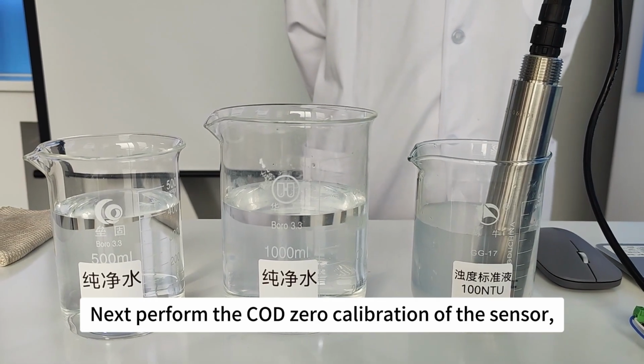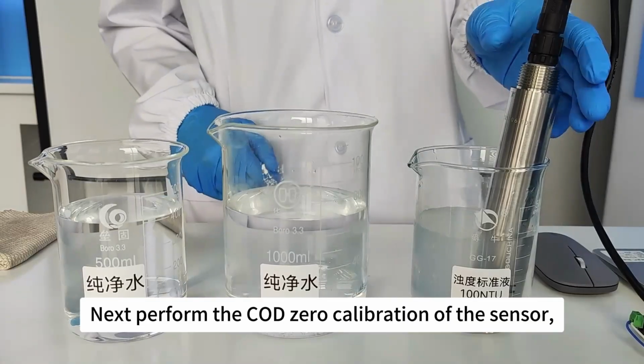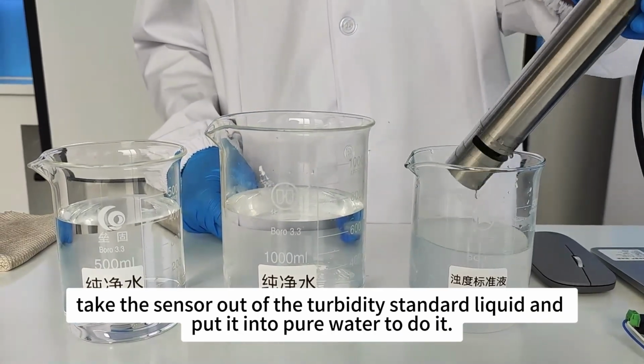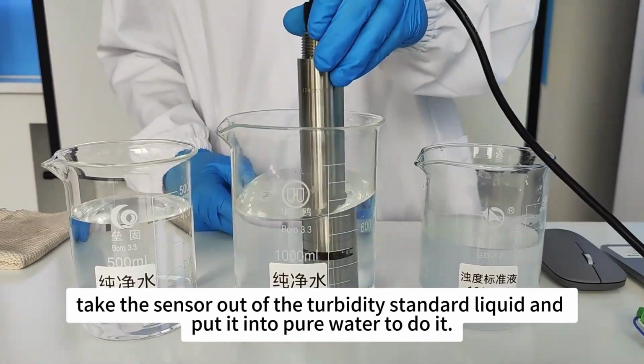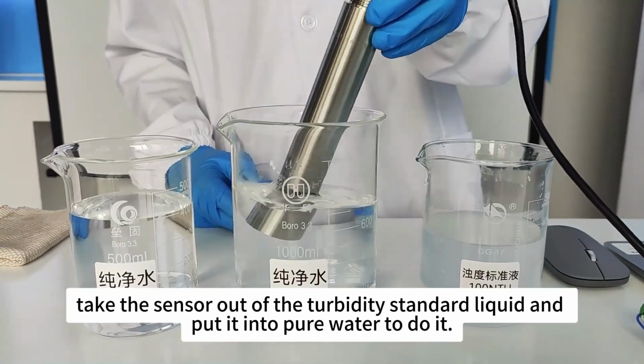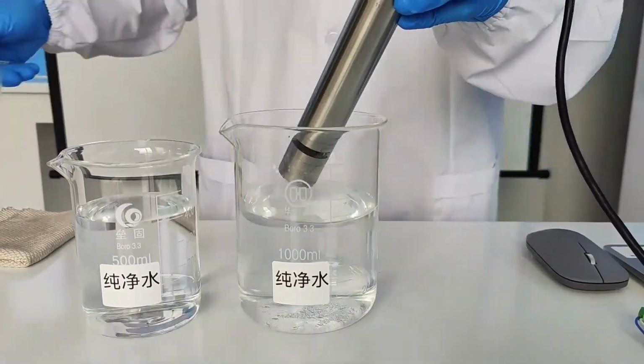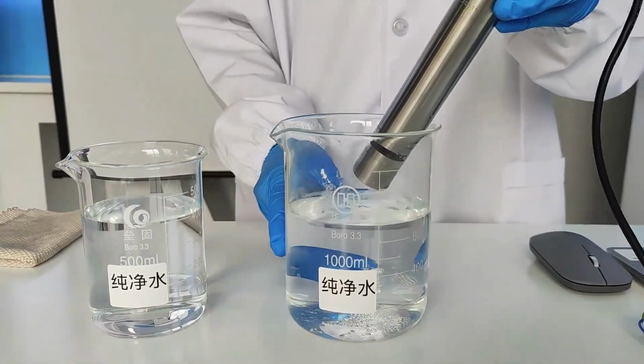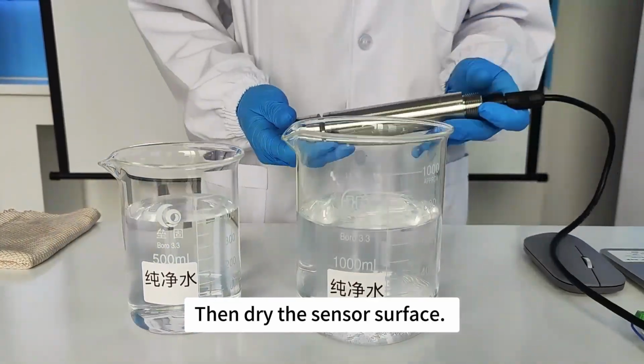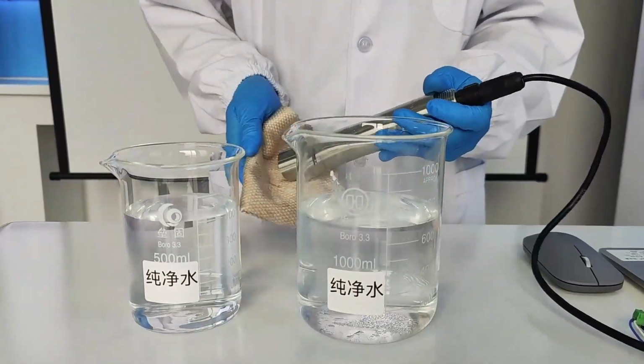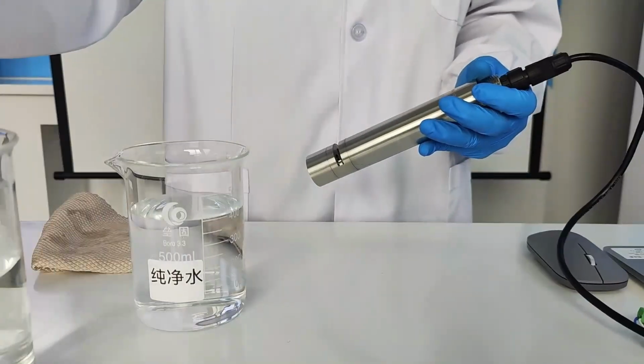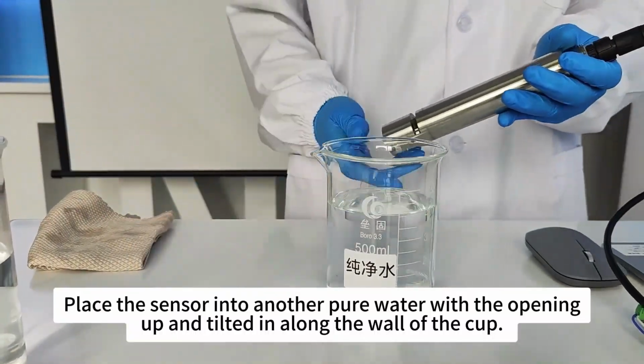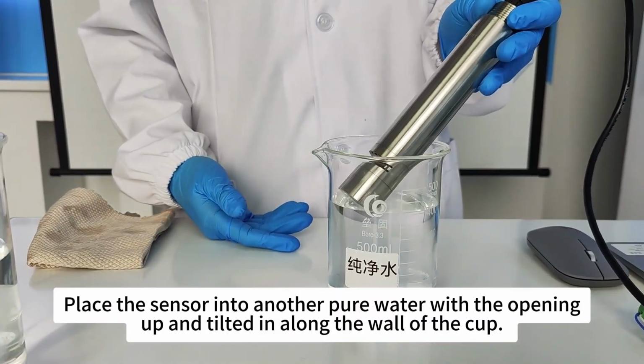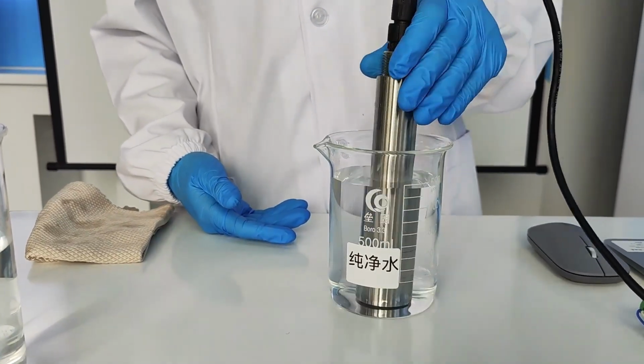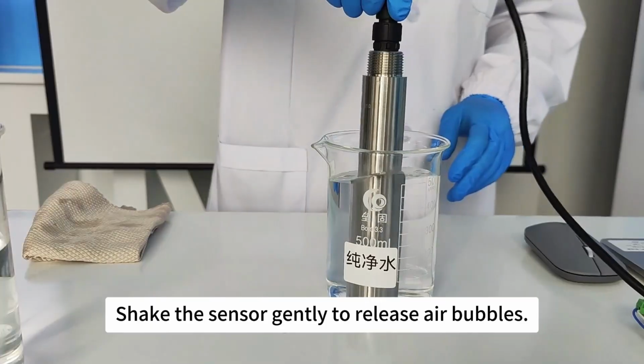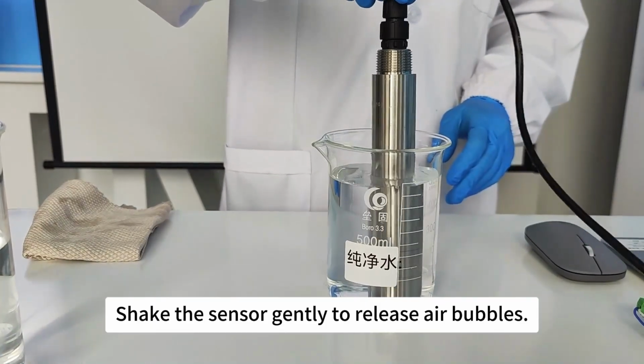Next, perform the COD 0 calibration of the sensor. Take the sensor out of the turbidity standard liquid and put it into pure water to do it. Then dry the sensor surface. Place the sensor into another pure water with the opening up and tilted along the wall of the cup. Shake the sensor gently to release air bubbles.